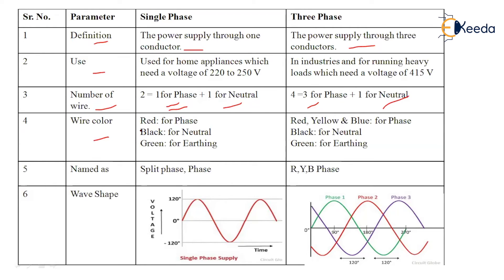The fourth parameter is wire color. In single phase, red is used for the phase or live wire, black for the neutral wire, and green for earthing. In three phase supply, red, yellow, and blue are used for the three phase or live wires, black for neutral, and green for earthing. The black and green wire meanings remain the same in both systems, only the number of wires changes, maintaining uniformity so any electrician knows which wire is used for what.